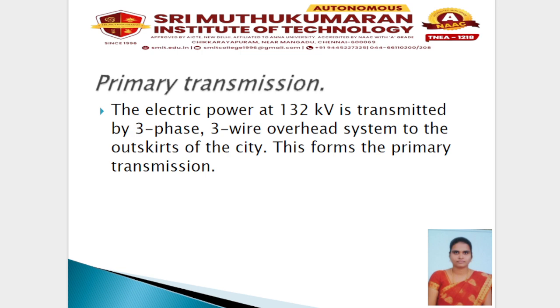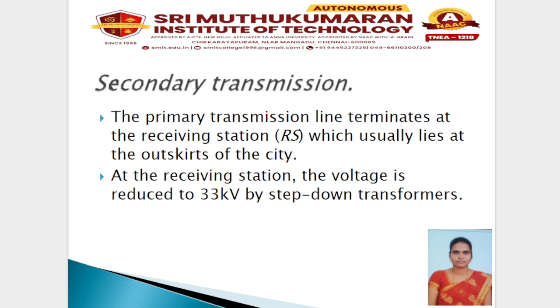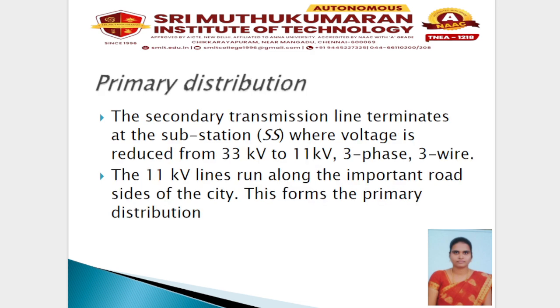Receiving station and secondary transmission. At the receiving station, the voltage is stepped down from 132 kV to 33 kV using step-down transformer. This is called secondary transmission. The reduced voltage minimizes losses and prepares power for further distribution within the city. Primary distribution. The secondary transmission lines terminate at substation where voltage is further reduced from 33 kV to 11 kV. These 11 kV lines run along major roads and supply power to local distribution substation. This stage is known as primary distribution.